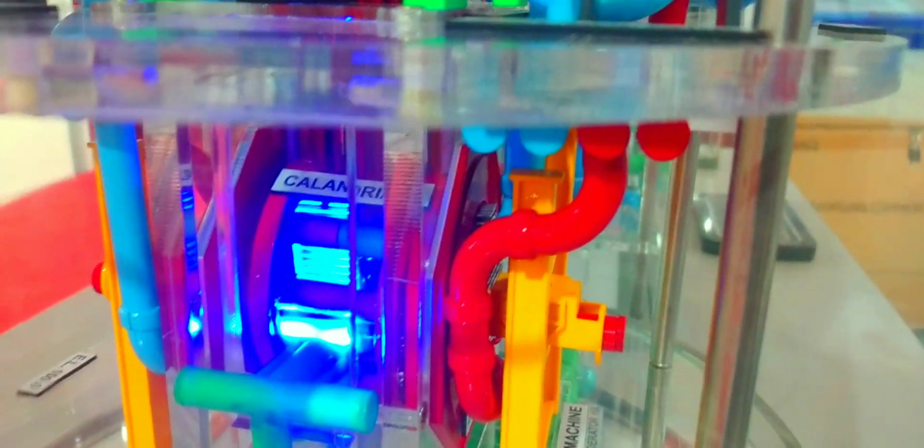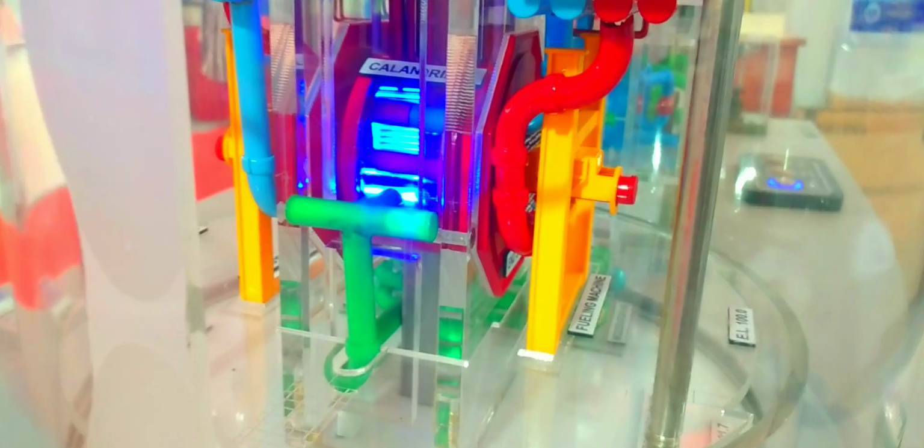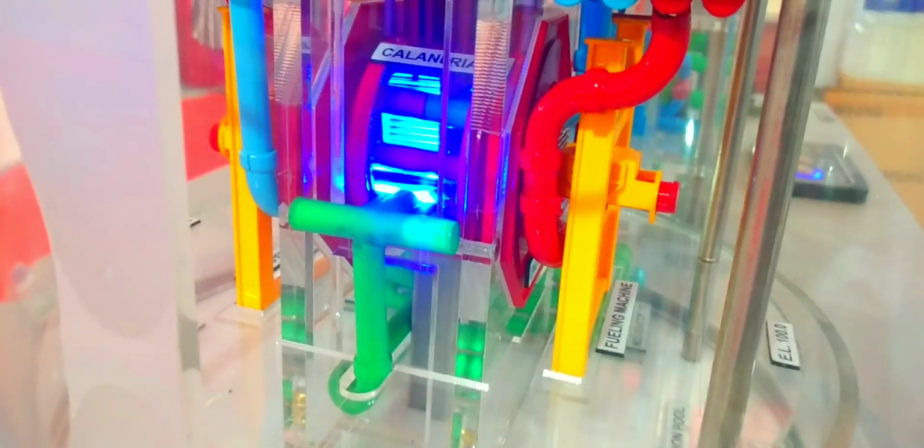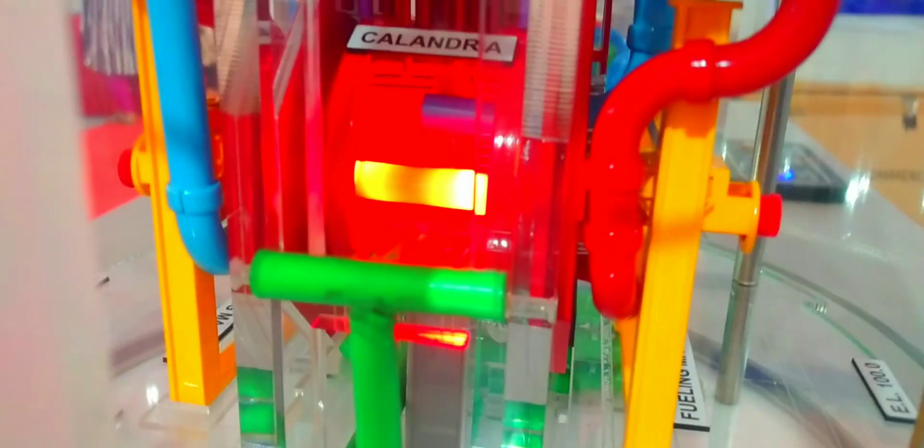It is a high-grade stainless steel vessel about 5.9 meters in diameter and 7.8 meters long. The calandria vessel is supported at both ends by end shields. Inside the calandria, there are 392 coolant tubes, also called pressure tubes.